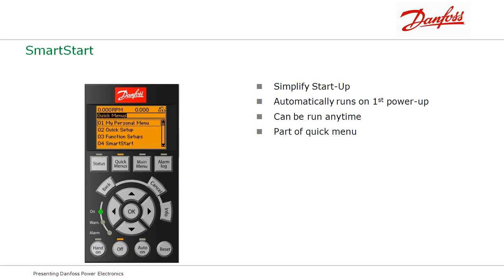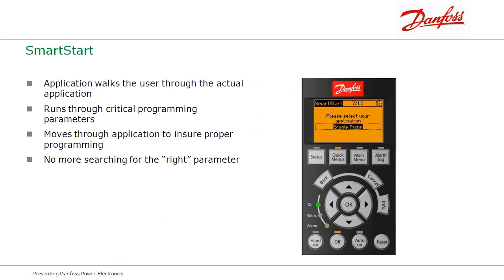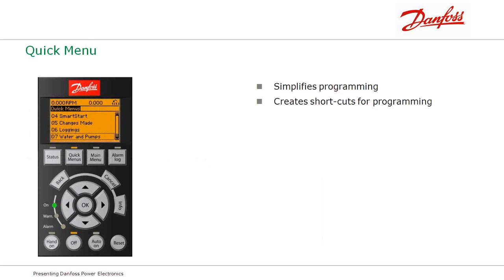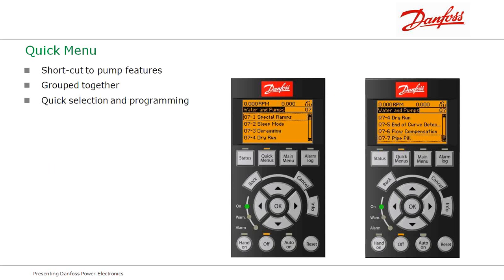And what we're looking to do here is simplify things, and part of what we do with some of our newer technology on programming is using Smart Start technology. Smart Start allows you to program the drive literally with a click of a button. You turn the unit on and it walks you through a menu-driven application so that you can program the drive. You don't have to search for specific parameters. You don't have to go through 300 or 400 parameters. You go through only the ones that you need to program based off of your application, utilizing, again, water and pumps and some of the specific questions that we see in our market.